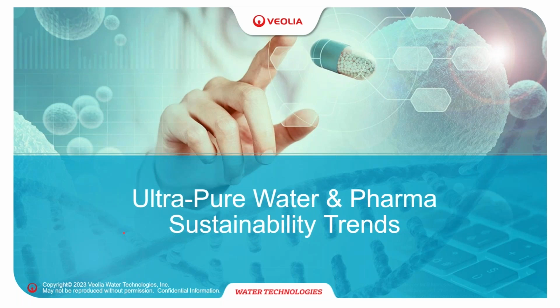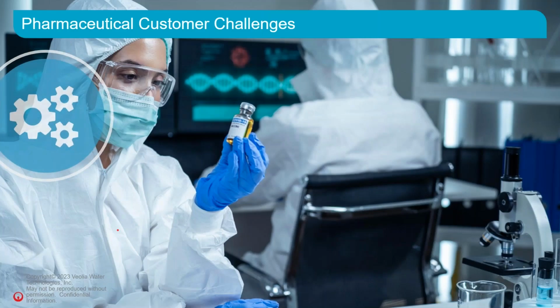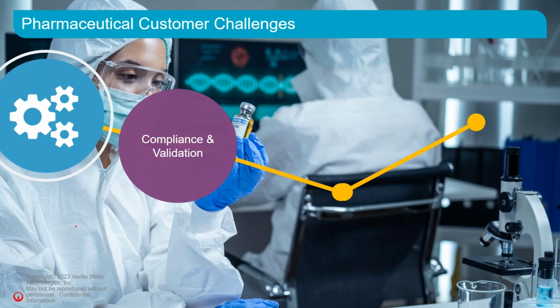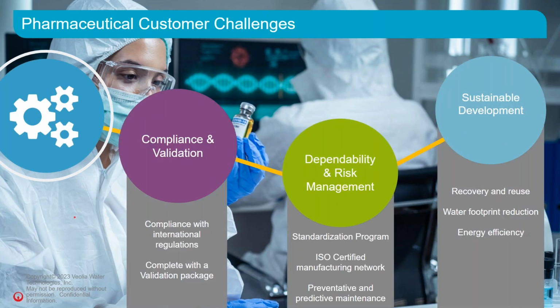So let's get on to the sustainability trends in ultra-pure water and pharma. Really, the challenges that the customers, as we see it, have are threefold. First and foremost, any product or system we're installing in this market must be compliant and come complete with some sort of suitable validation pack. And we make sure in any of the products and solutions we supply that they are designed in terms of compliance with the international regulations, so things like the ISPE, GAMP, CGMP, ASME BPE, and then the water quality is in line with things like the USP, European Pharma, Japanese Pharma being the big three. So we ensure that those guidelines and water qualities are taken care of.